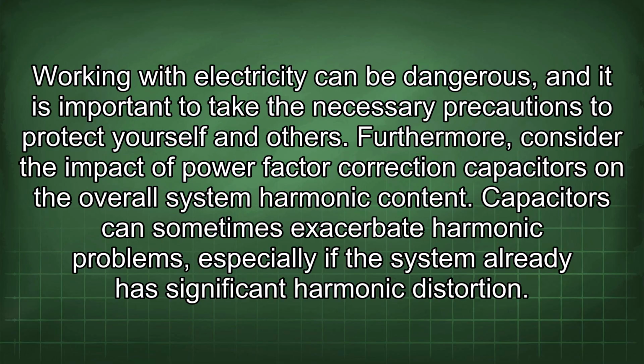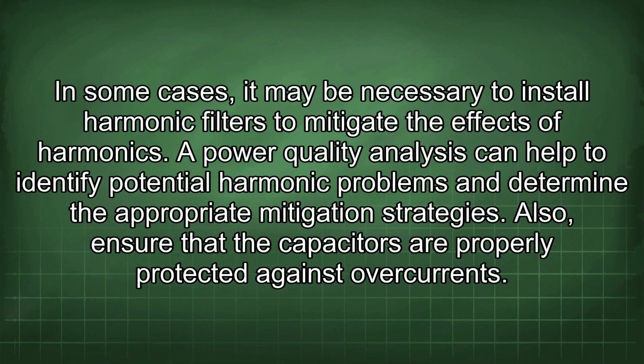Furthermore, consider the impact of power factor correction capacitors on the overall system harmonic content. Capacitors can sometimes exacerbate harmonic problems, especially if the system already has significant harmonic distortion. In some cases, it may be necessary to install harmonic filters to mitigate the effects of harmonics. A power quality analysis can help to identify potential harmonic problems and determine the appropriate mitigation strategies.